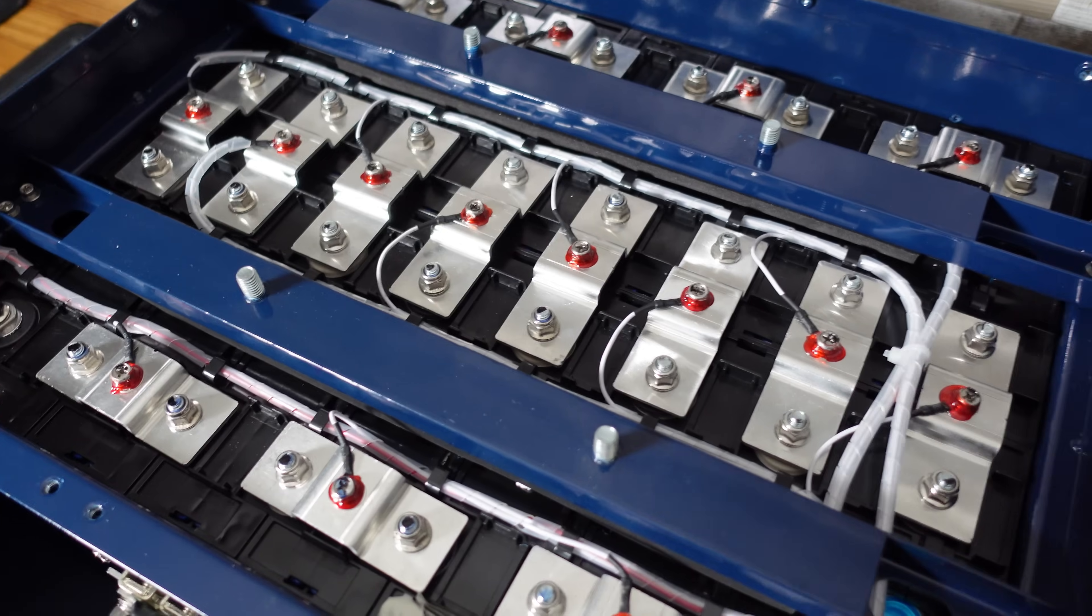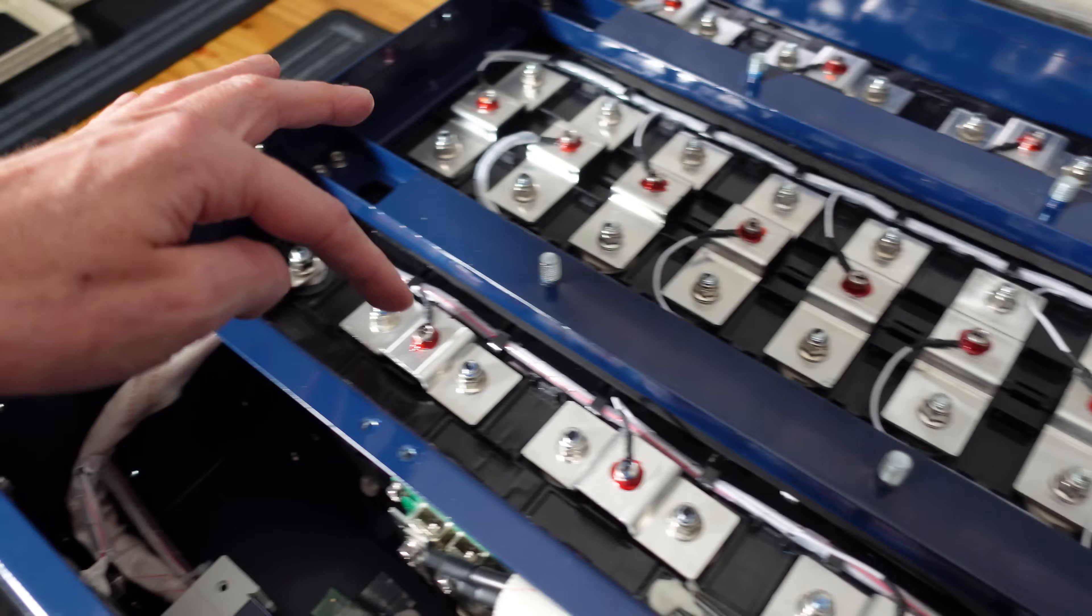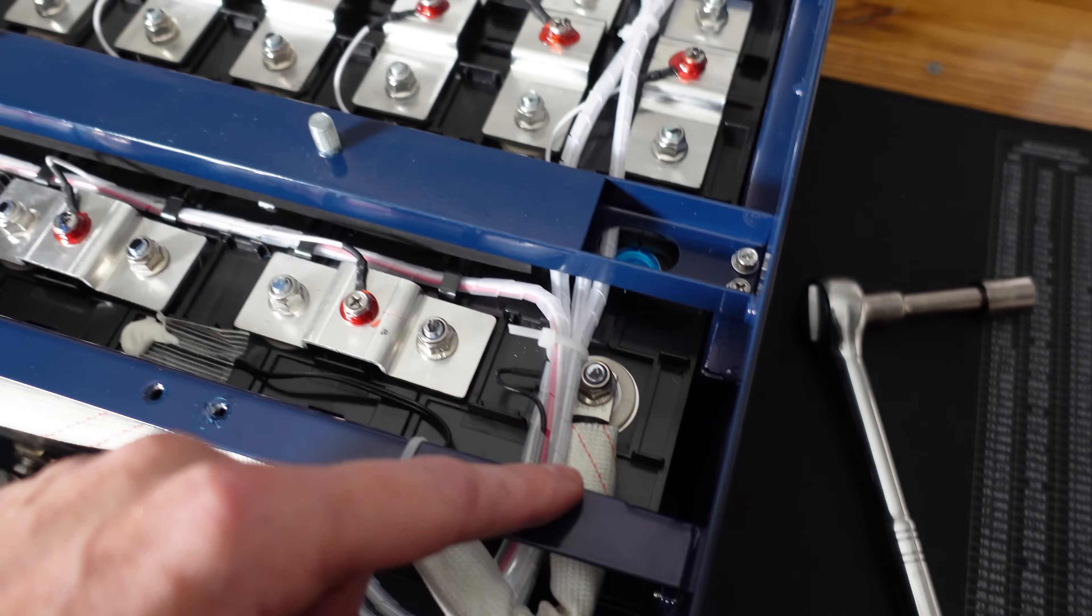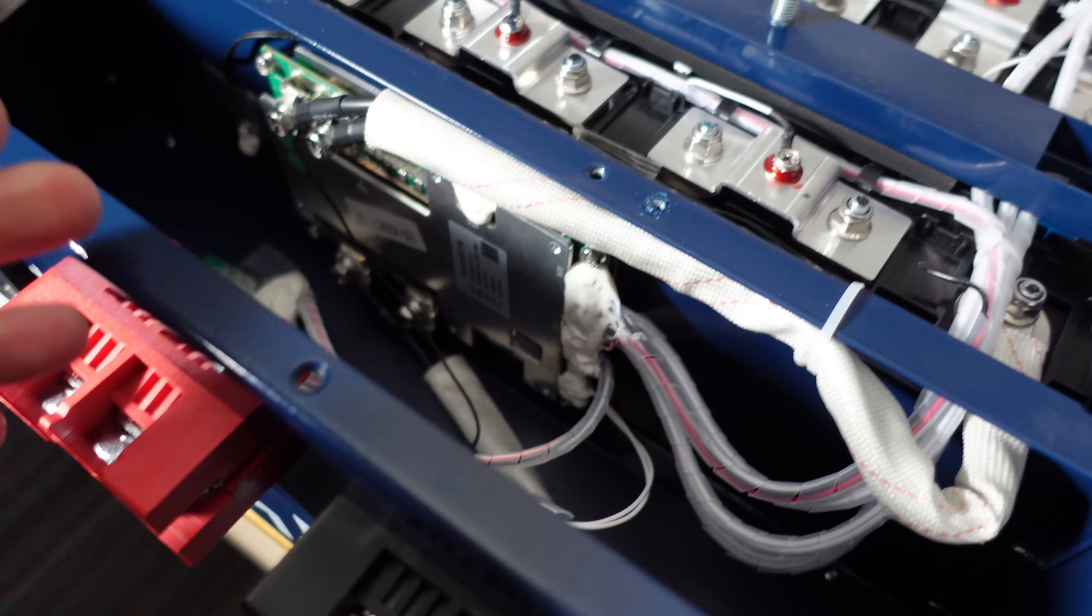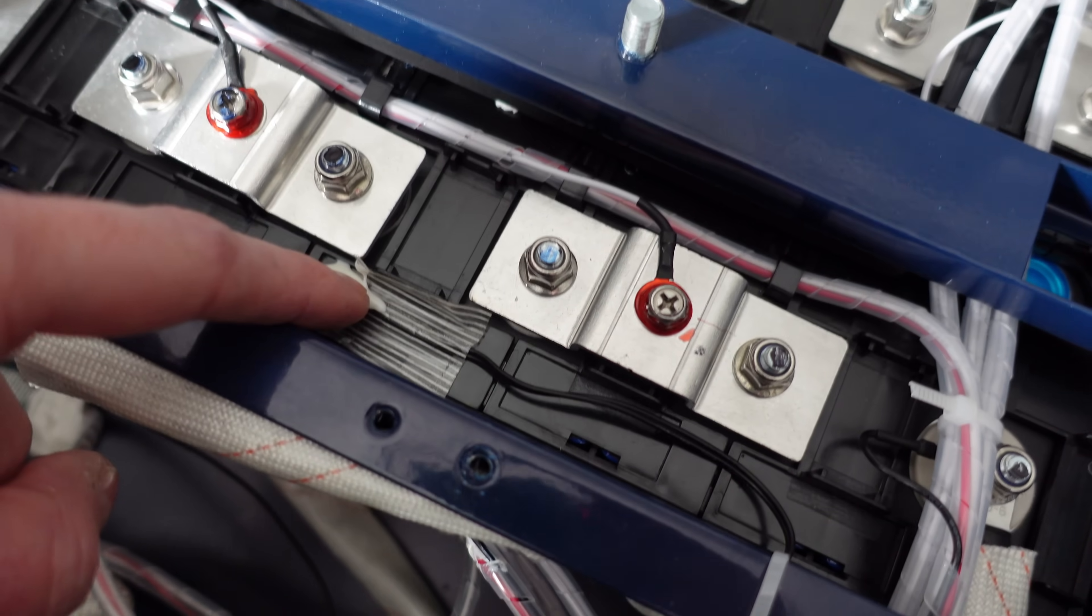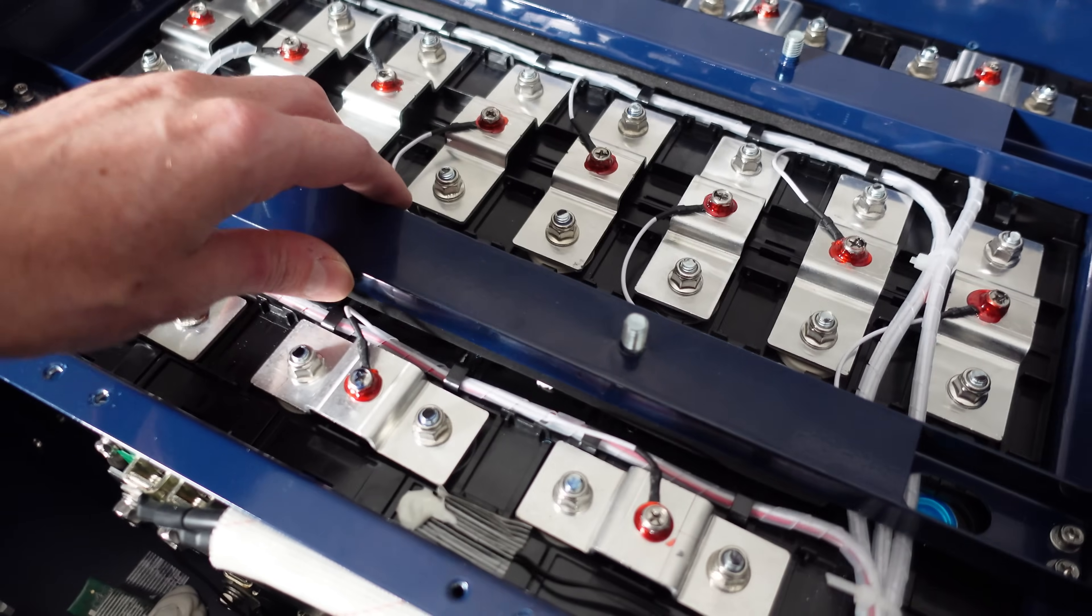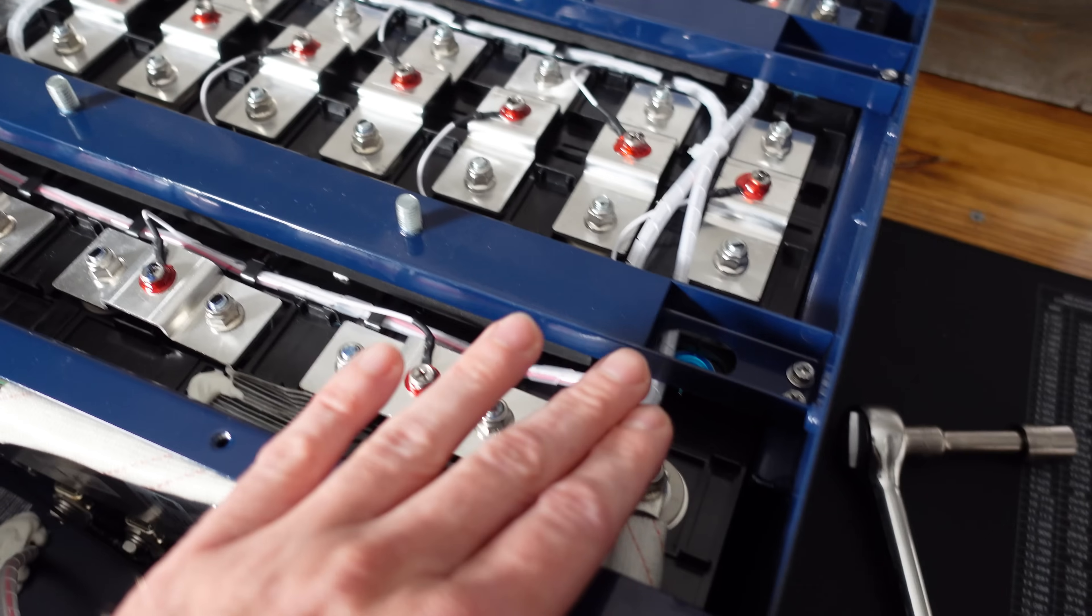So there are 16 cells here. This is the main positive and they sort of zigzag around the case here with how they are connected all the way back to the lower right here where we have the main negative and where all the balance leads come back through. I can see our BMS down in there. It does look like a JBD BMS. It's not the typical Pace that we've seen on rack mount batteries, but I see we have one temperature sensor on the battery here in the front. I do like seeing good structural support in these cases and these are some heavy duty support braces they have going across here.